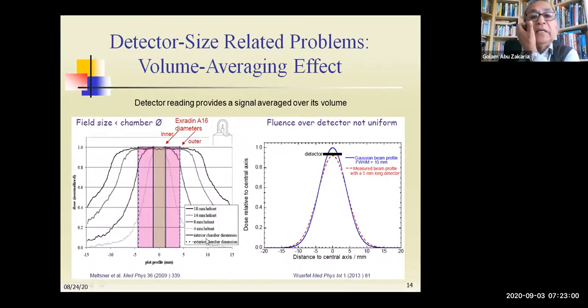the dose by 0.5%. When the field size is smaller, then the underestimate is also larger. So here, once again, the volume averaging factor: on the left side, you see the dimension of a detector and different types of distribution according to the fields here. When the field is small, then you have more error, more volume averaging, and when the field is larger compared to the detector, then you have less. And it is shown in the right pictures in one dimension.